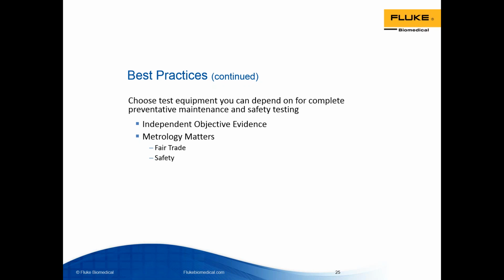Safety. We depend on measurements for medical, electrical safety and minimum performance standards. Legal requirements. Manufacturers and hospitals have a legal responsibility to keep records to show that medical devices and test instruments used to evaluate them are accurate and traceable. Interoperability. Measurement parameters for medical devices manufactured in Asia should be correlated to the measurements performed in the U.S. Traceability. Interoperability depends on all measurements being traceable to a single reference point. And finally, consistency and quality. We want to remain consistent and accurate in order to build and test products with quality. So that's why metrology matters, and the test equipment that you use also matters.